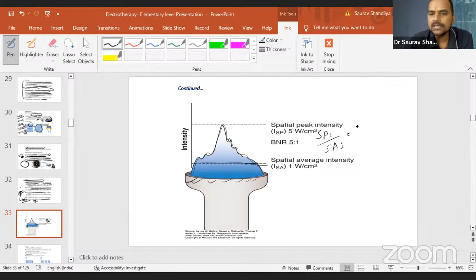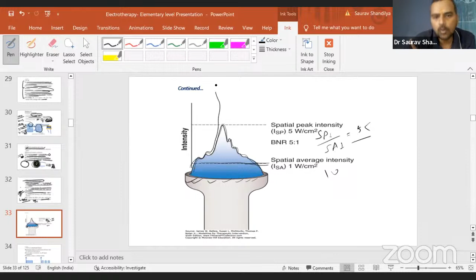Suppose it comes to this level. Now the highest was at this level. So you divide spatial peak intensity by spatial average intensity. If you get a ratio of 5 or less than 5, your machine is good. Suppose this ratio is 10. That means this particular thing will go here and come. Is it good for the patient? No, it is bad for the patient because your machine is not working properly. I hope every one of you understands.